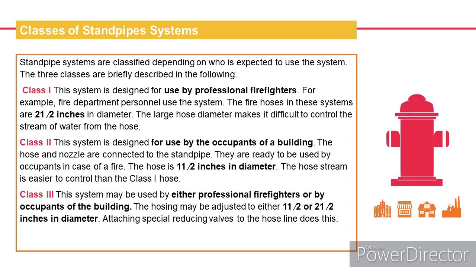Class II. This system is designed for use by the occupants of a building. The hose and nozzle are connected to the standpipe. They are ready to be used by occupants in case of a fire. The hose is 1 1/2 inches in diameter. The hose stream is easier to control than the Class I hose. Class III. This system may be used by either professional firefighters or by occupants of the building. The hosing may be adjusted to either 1 1/2 or 2 1/2 inches in diameter. Attaching special reducing valves to the hose line does this.